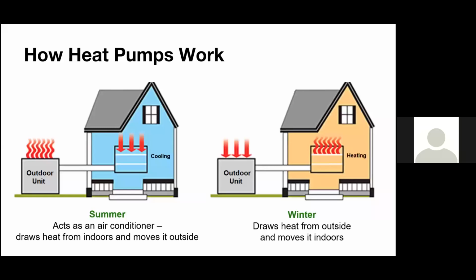There's defrost cycles that'll happen, but the good news, when it gets really cold, 0 degrees, there's just not that much water left in the air. So the defrost cycles are a bit more rare, but in the 25 to 40 degree Fahrenheit range, outdoor temperature, that's going to be when more of the defrost cycles come into play, when you're looking at an air source heat pump and how much heat you can get. So any manufacturer software properly takes that into account when selecting and sizing the equipment. But again, it's just something else to keep in mind.